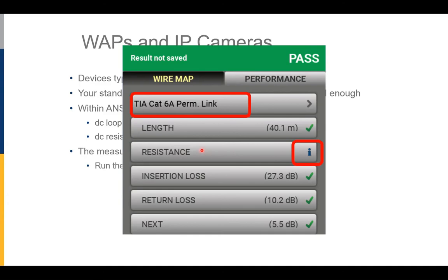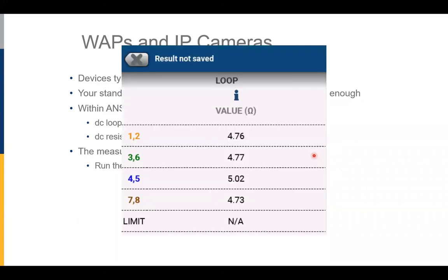We always measure resistance. Our electrical engineers in the factory are kind of hung up on this, but we're just calling it informative because there's no limit. It's not required by the standards. So I can't say whether these values pass or fail.